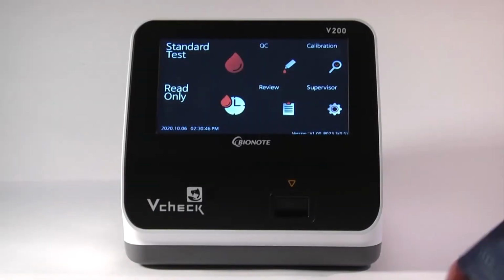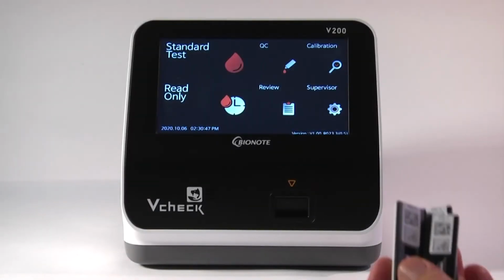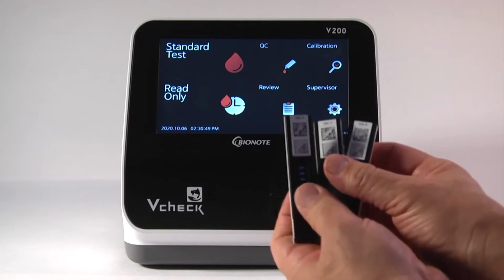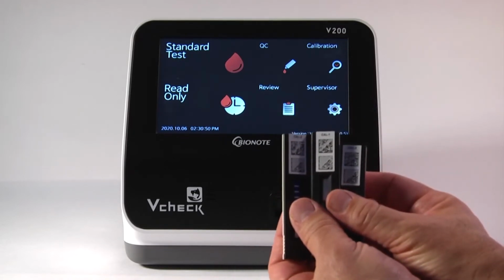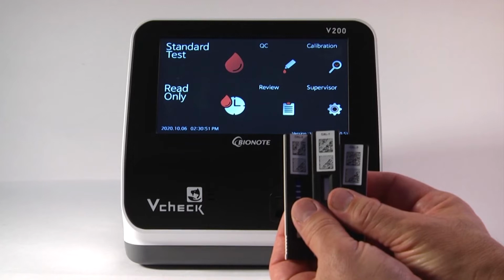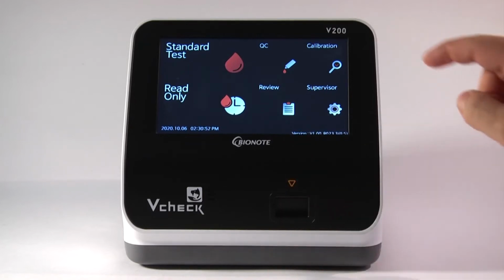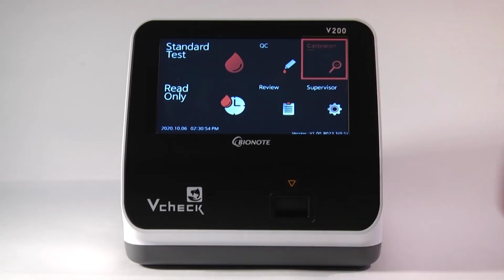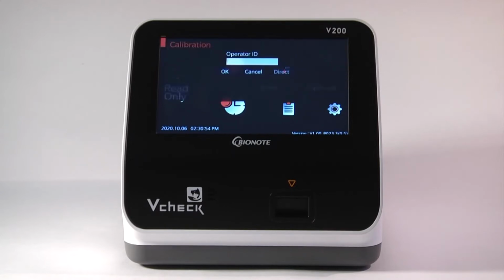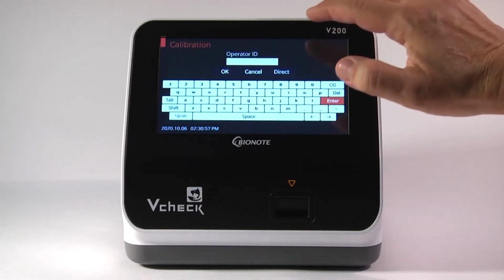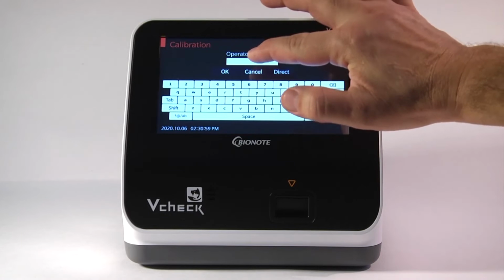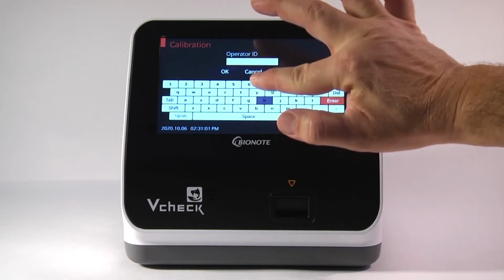To calibrate, open the calibration set that came with the analyzer. You have 3 devices, a Cal 1, a Cal 2, and a Cal 3. To start the calibration, touch the calibration icon from the main menu. Enter the operator ID, then press OK. You can also perform the calibration using the direct option.